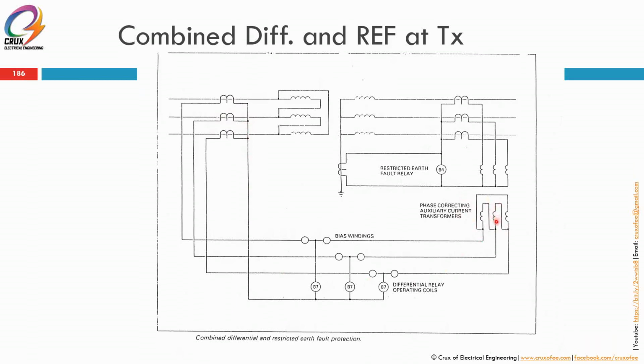This is to interpose the vector of the current. If not, there will be a differential current. If you just connect it normal, like star point to star point, there'll always be a differential current. This is due to the fact that it's a delta star connection. It has already been shifted, maybe by 30 degrees, depending on DYN11 or DYN1. So we transpose the connection to compensate that angle.